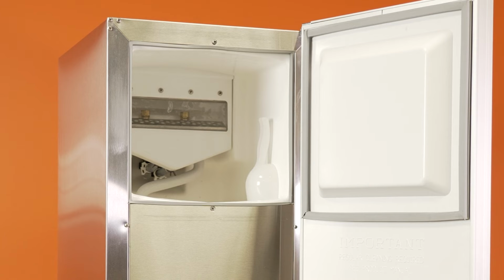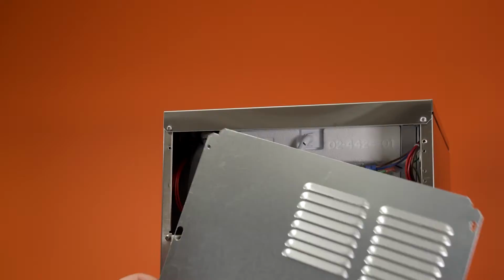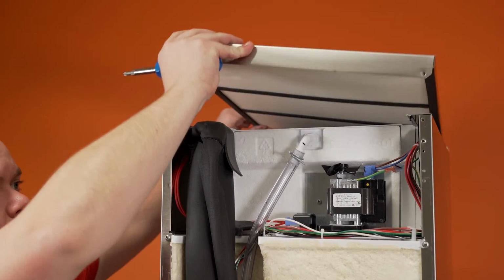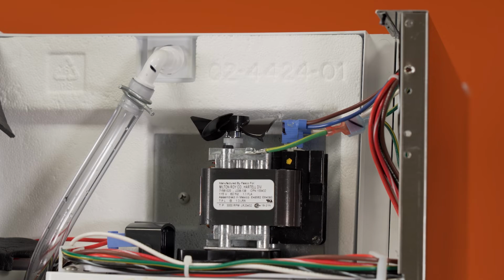If the machine is making ice but not releasing it from the evaporator during harvest, the hot gas valve may not be fully opening and not providing enough hot gas to successfully harvest the cubes. Remove the service access panel and then wait for the machine to enter harvest, which is easily identified by both the spray pump and the condenser fan being off.